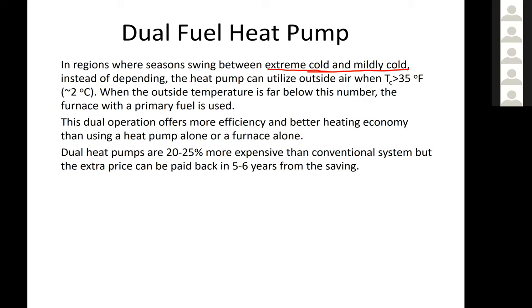Then the heat pump at that point is going to be useful as long as the outside temperature is greater than 35 degrees Fahrenheit or about 2 degrees C. When the outside temperature drops far below this figure, then in that case, I should use the furnace. I need to use a primary fuel as a source of heating. It's going to be more economical than using a heat pump, because when I use the heat pump, I'm going to use electricity at an efficiency not as high as using the furnace.